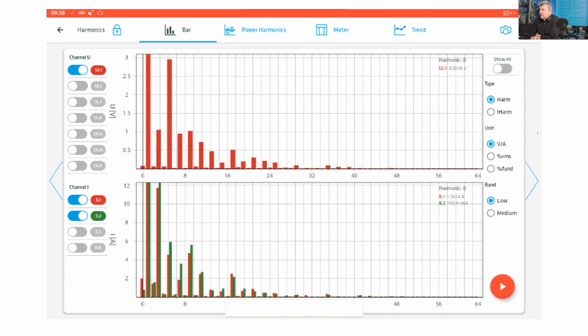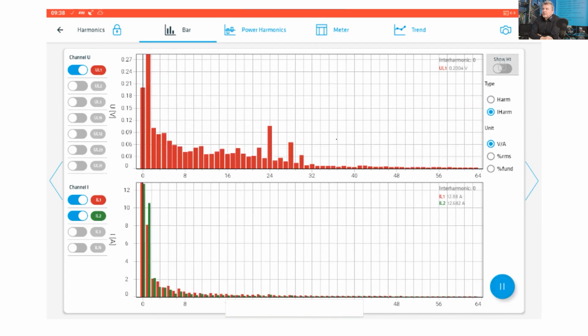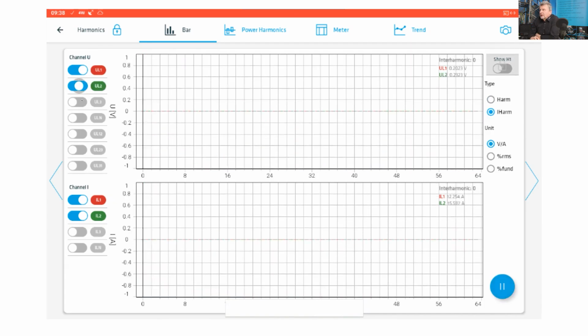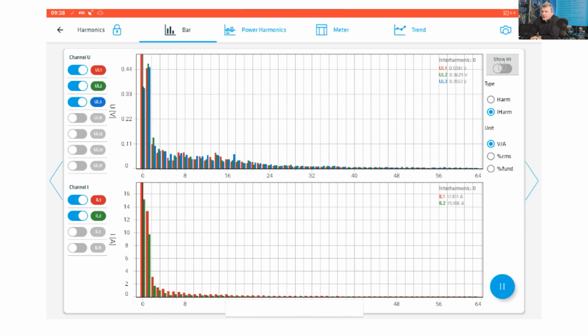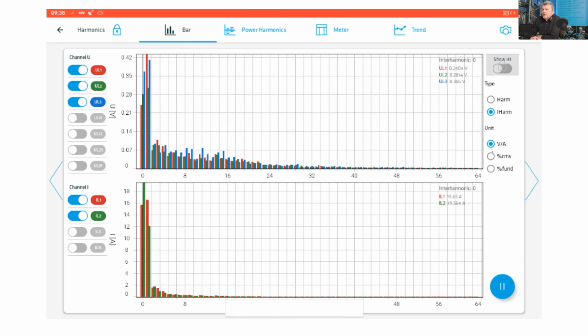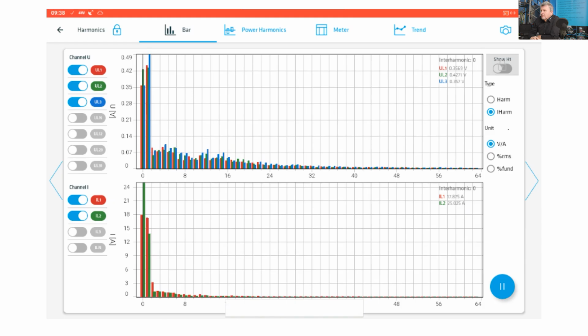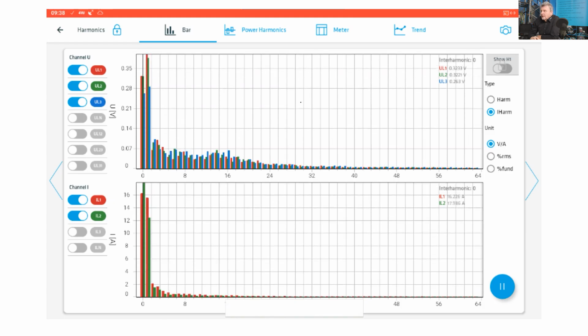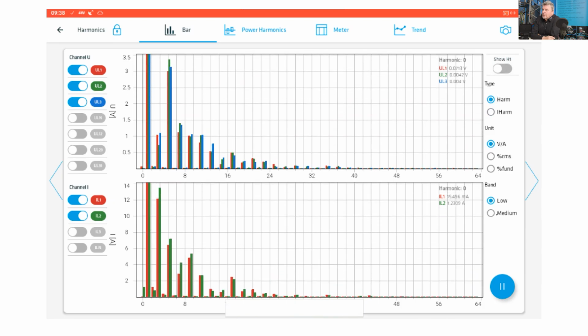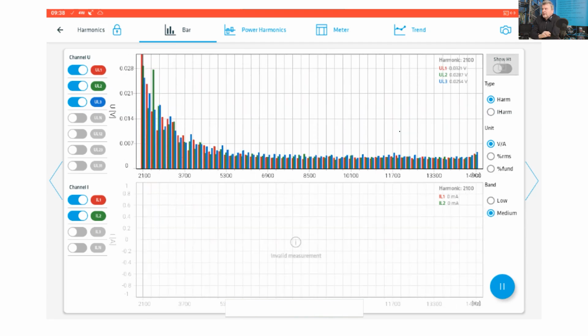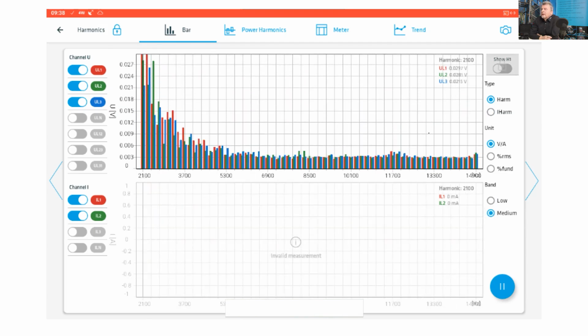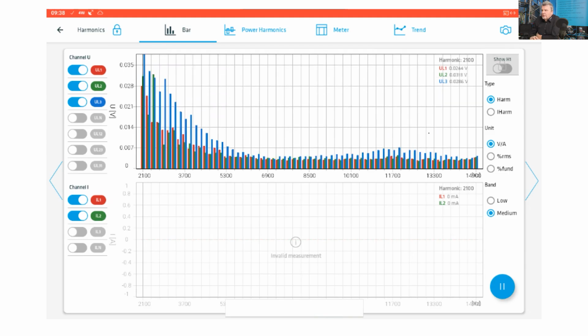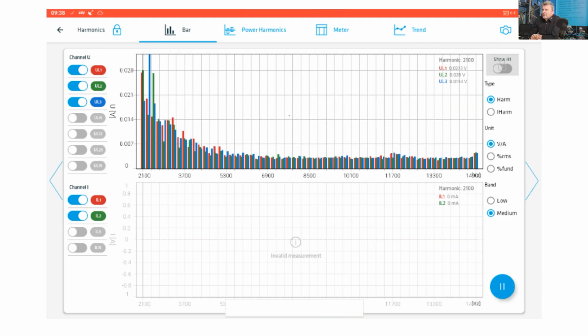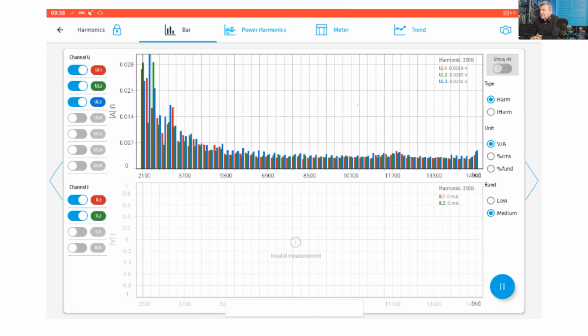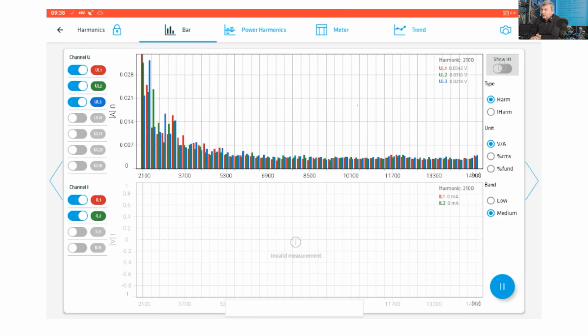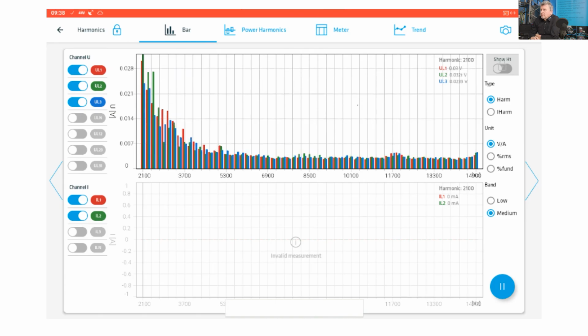You can then switch to the interharmonics view for the voltage and currents. Also, interharmonics can be presented as absolute value or related to the RMS or fundamental. A specific one is supraharmonics. Supraharmonics are presented only for the voltages, since most of the current clamps do not support frequencies higher than 4 kHz. Specific current clamps should be defined if you want to measure supraharmonics.